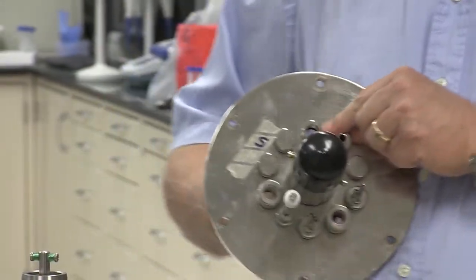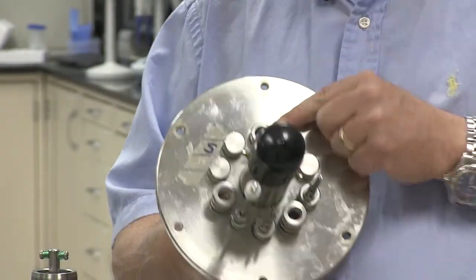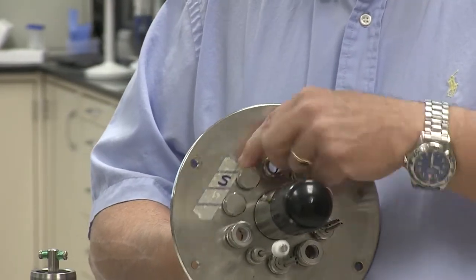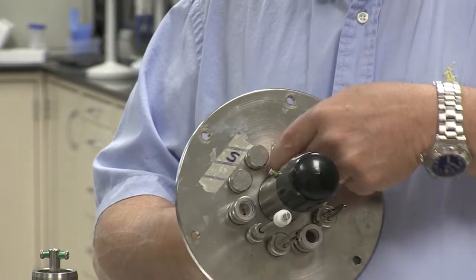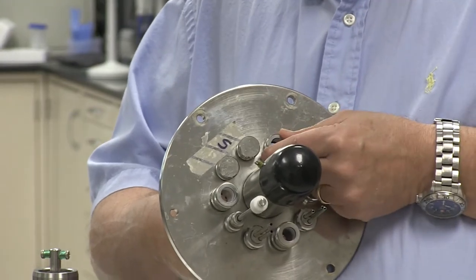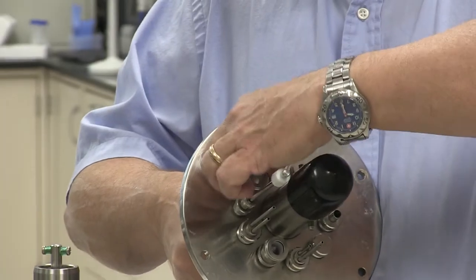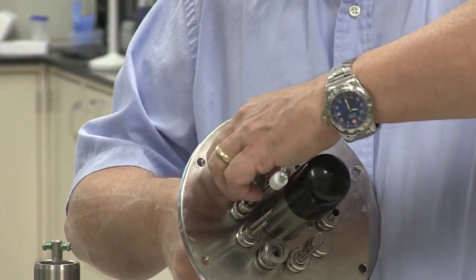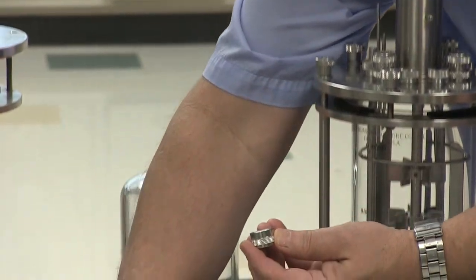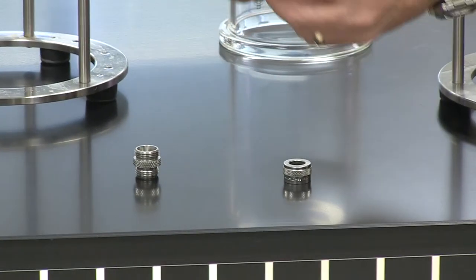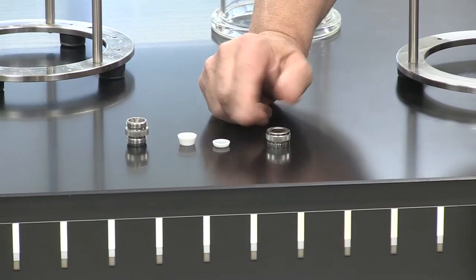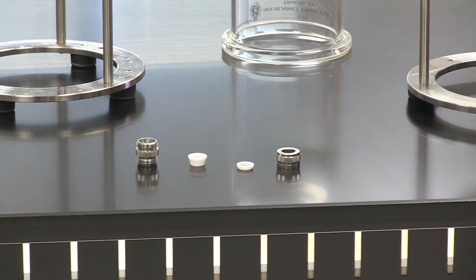Okay. Then there's this kind of port here. This is for the exhaust condenser. We'll be talking about that in a bit also. But it's just an open stainless steel fitting that has three set screws in it that allow it to clamp down on the stainless steel condenser. These other two ports here are multi-part ports. They're actually, let me take one out here. They actually have two metal parts, and then inside there's a Teflon ferrule. Right, and it's two parts, and these are used for the pH probe and the DO probe.